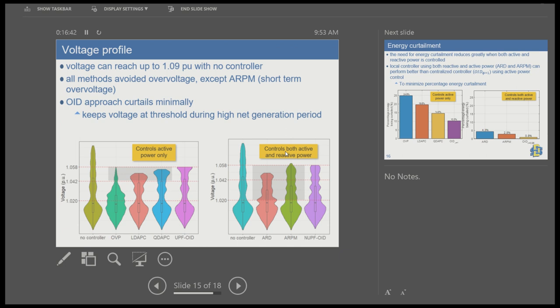The OID approach, being optimization-based, does the exact amount of curtailment necessary, so the voltage sits exactly at the threshold limit while minimizing curtailment. The other controllers maintain voltage below 1.058. The box plots cluster voltage magnitudes based on frequency of operations, combining data from all houses. The left-hand side shows results for active power control only, and the right-hand side shows results for combined active and reactive power control.